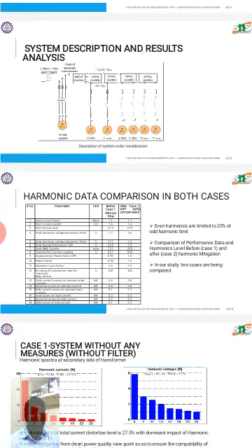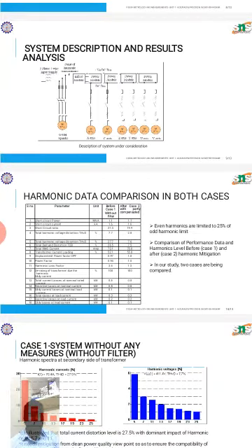Harmonic mitigation: in our study, two cases are being compared. Case 1 is a normal system configuration interfaced with CNC, AC servo drive, spindle drive, along with adaptive and in-process gauging system, high voltage module, isolation transformer and switchgear items. In case 2, additionally a partially compensated filter is added to reduce both system THVD and THID levels. The comparison is given in the table below: harmonic data comparison in both cases.